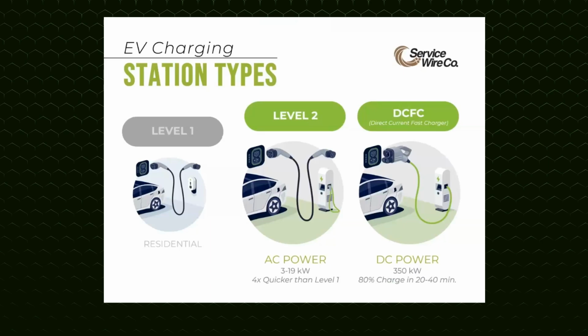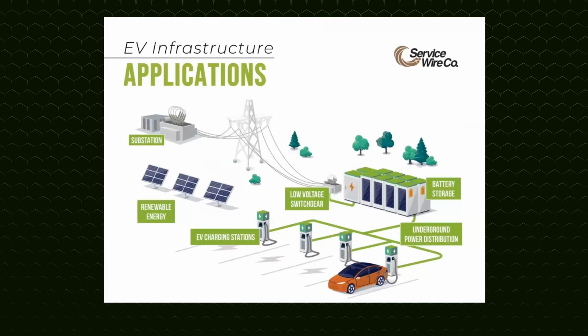Direct current fast chargers, or DCFC superchargers, are the fastest chargers available with a maximum output of 350 kilowatts. They are designed to fill an EV battery to 80% in just 20 to 40 minutes. Keeping commercial charging stations in mind, let's break down this application. EV charging stations are powered by either renewable energy, fossil fuels, or utilities. Medium voltage cables connect power sources, like the PV panels or on-site battery storage, to substations and transformers. Transformers will then step this down into low voltage.